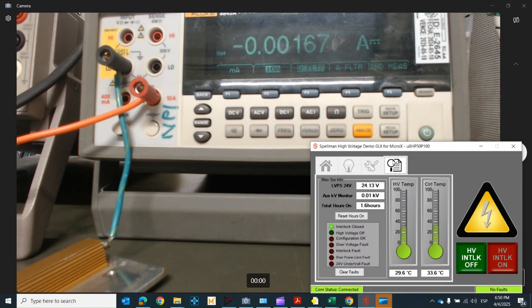The following test to be performed is the self-diagnostics test, which will be carried out mostly in interaction with this screen, which contains all the fault information and general operating conditions of the unit, such as input voltage and temperature. We will be testing for the over-voltage protection fault, the interlock fault, the overpower fault, and the under-voltage fault.